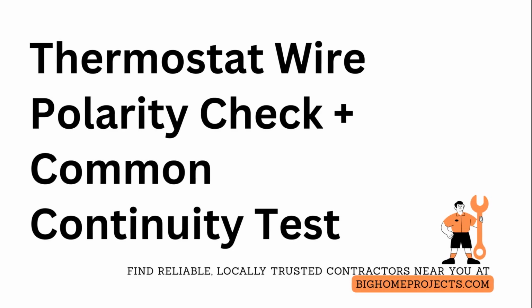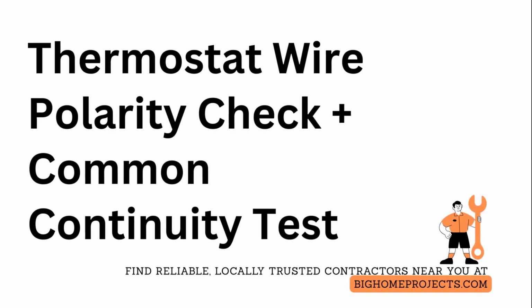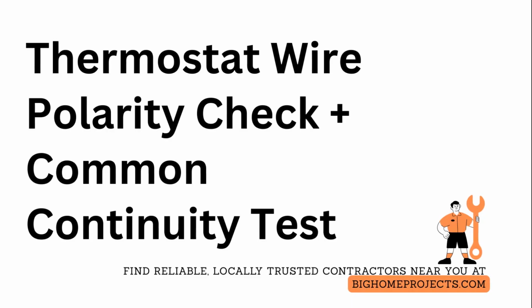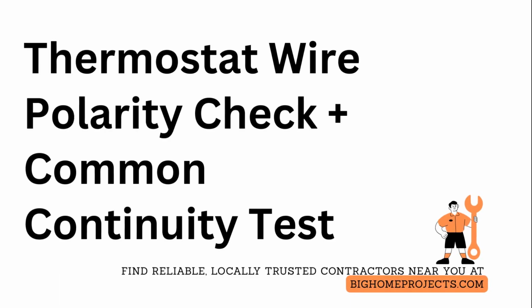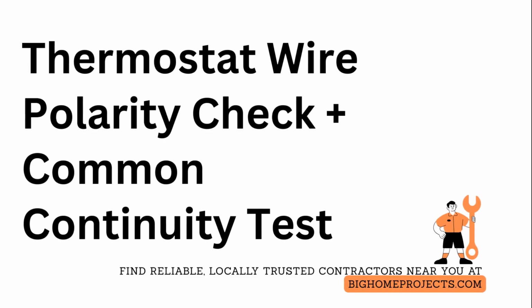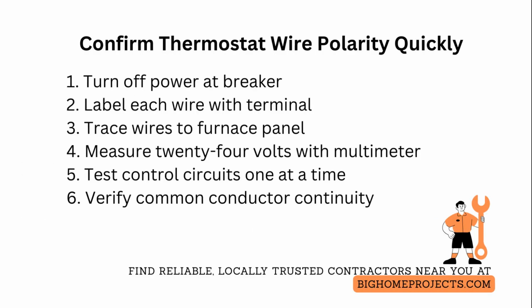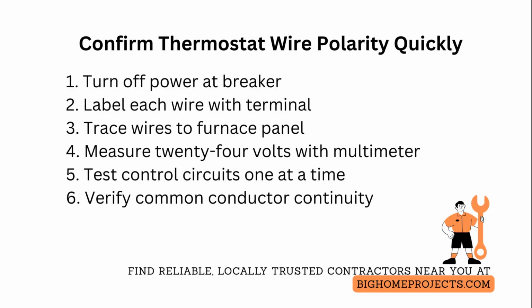Confirm thermostat wire polarity and function before powering the system to prevent damage, repeated mistakes, and costly repairs when a previous installation looks suspect. Start by turning off power at the circuit breaker and the furnace switch, then remove the thermostat faceplate and label each wire with its terminal letter using removable tape so you have a clear map.